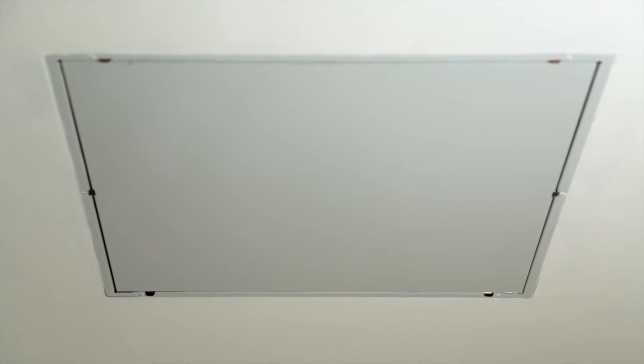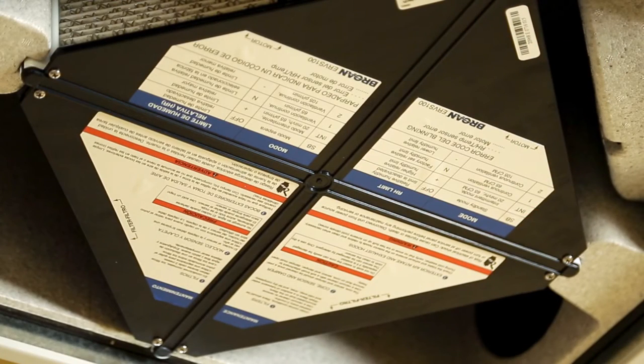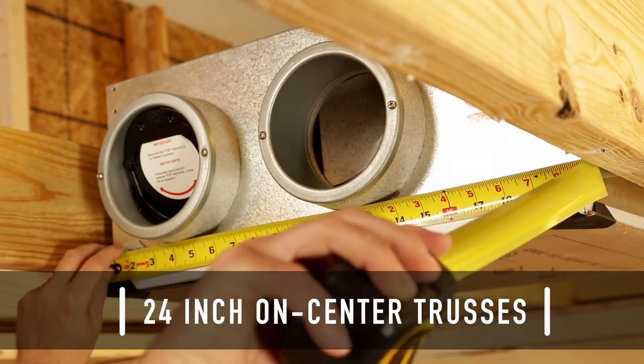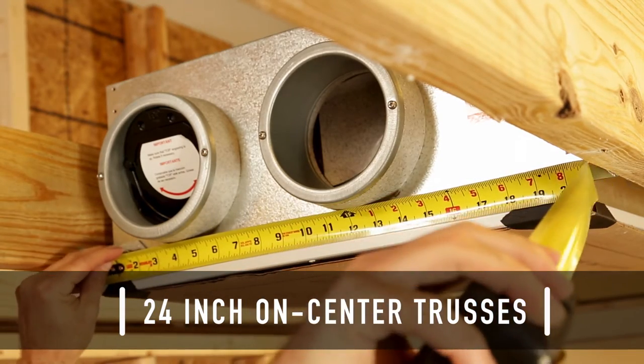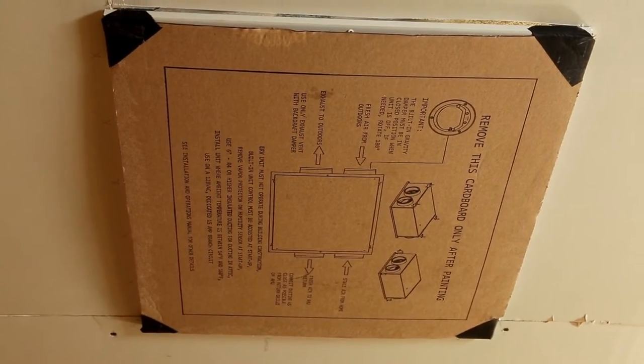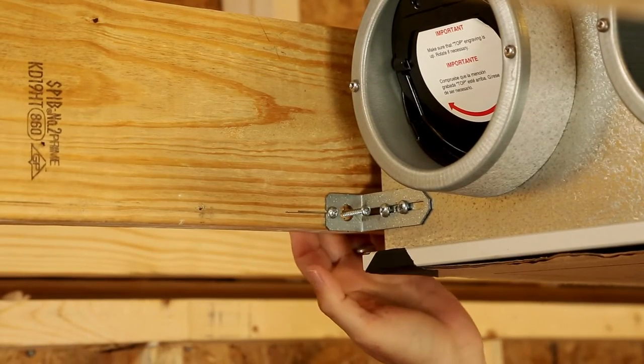Mounting the ERVS-100 in the ceiling makes it easy for homeowners to perform system maintenance from within the living space. When mounted in the ceiling, the system is installed between 24-inch on-center trusses. The ERVS-100 is designed for optimal installation during the construction phase of a home. Install between trusses prior to the installation of drywall on the ceiling.